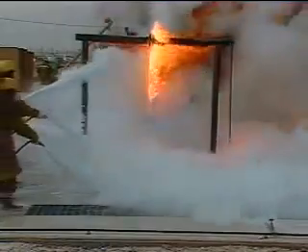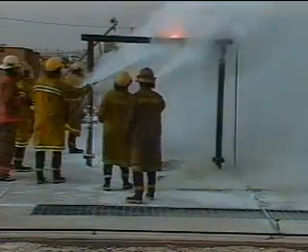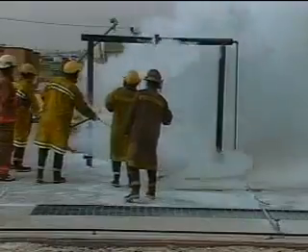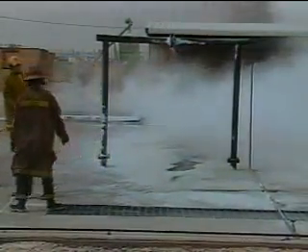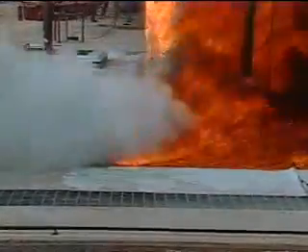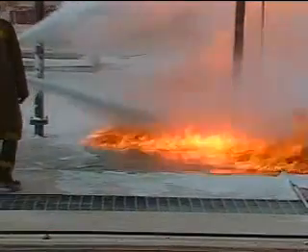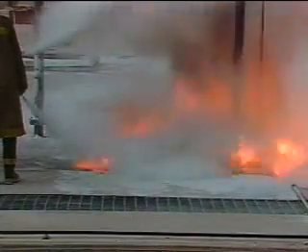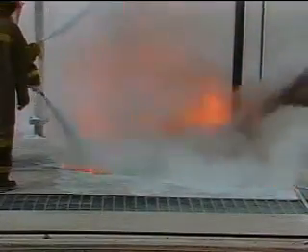You want to corner the fire, so begin on one side of the fire and sweep the nozzle back and forth, continually pushing the leading edge of the fire away from you until it's out. Expect an average stream reach of approximately 8 to 10 feet, depending on the extinguisher. Watch closely to make sure you're actually hitting the fire with the extinguishing agent.